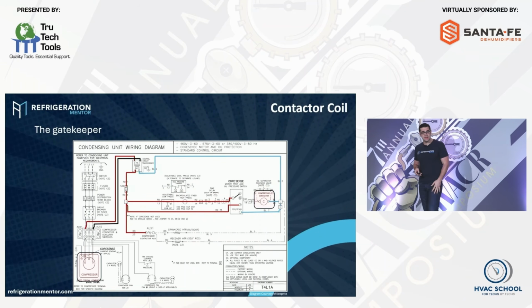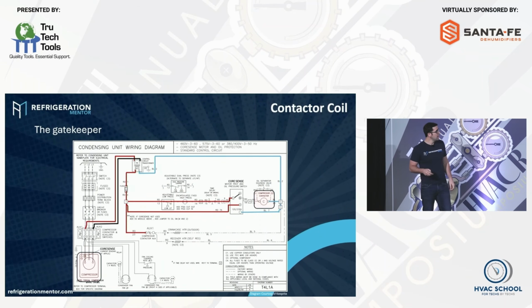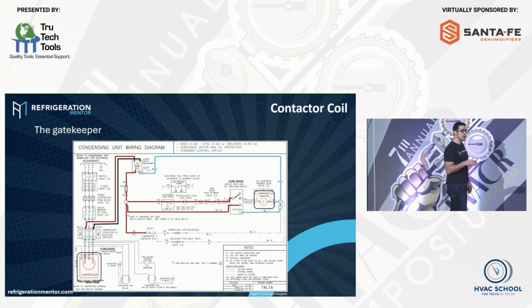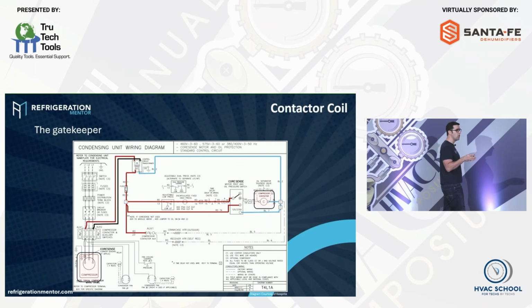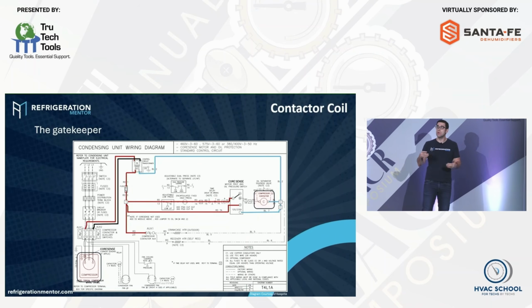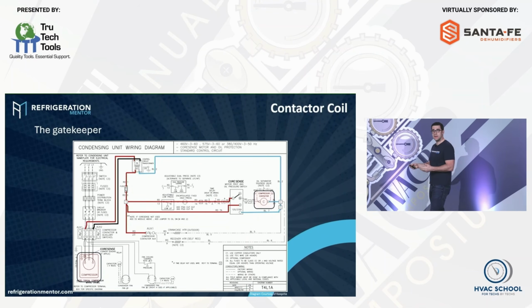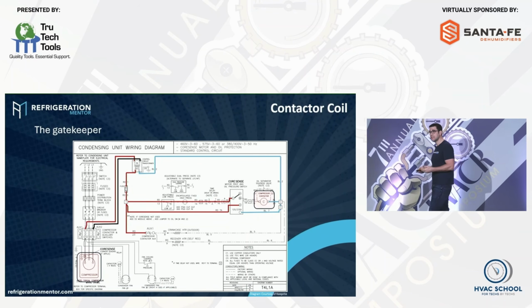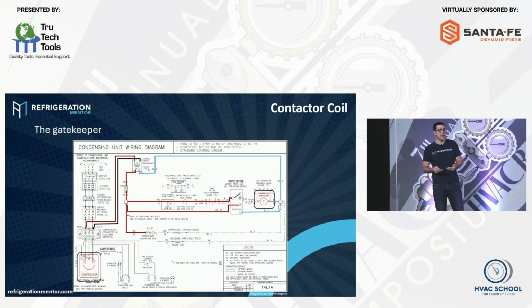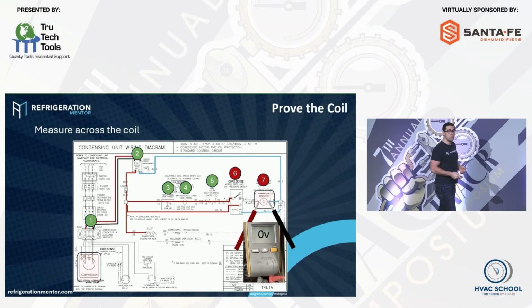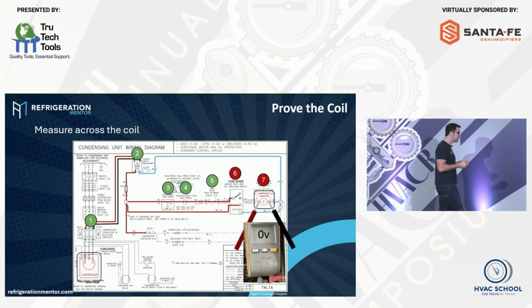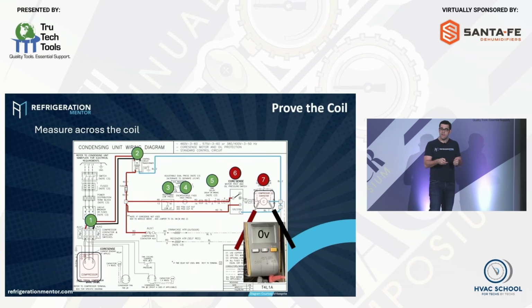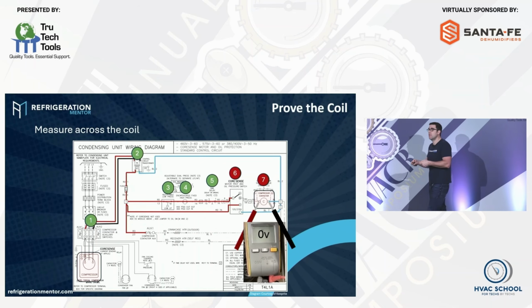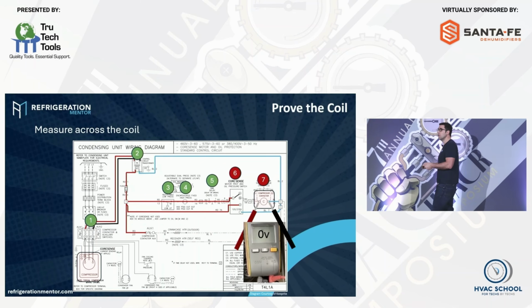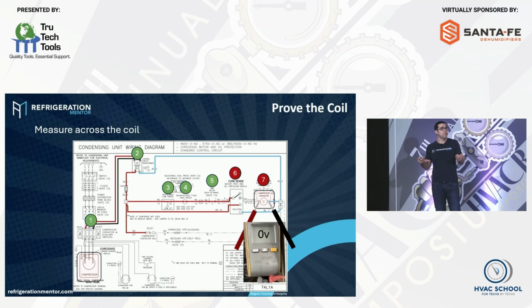Contactor coil is the gatekeeper. And really, what we want to know is, do we have power to that coil, and is it actually doing the action that we want, by pulling in the contactor contacts to make the circuit, okay? If that is not happening, we've got to prove it. We've got to take our meter out. Do we have voltage there or don't we have voltage? In this example, it says 0 volts. We don't have voltage to that coil, so that's not going to pull in. So what could be the problem?